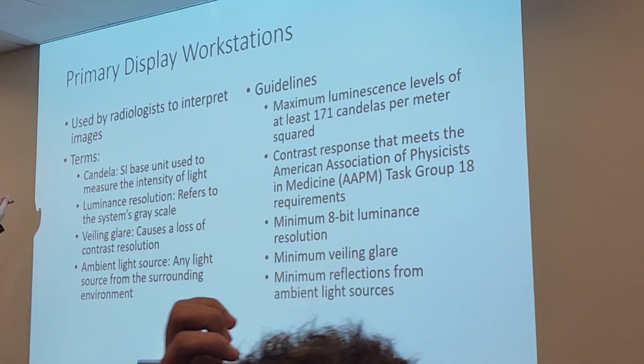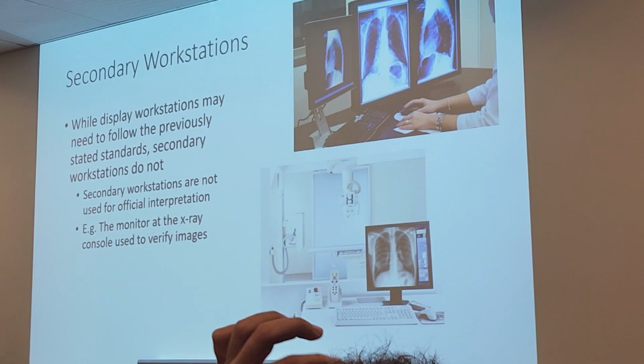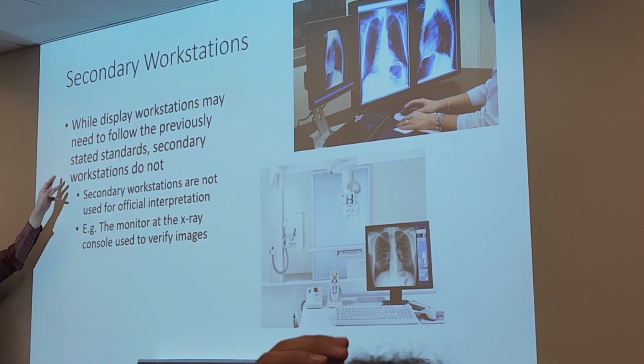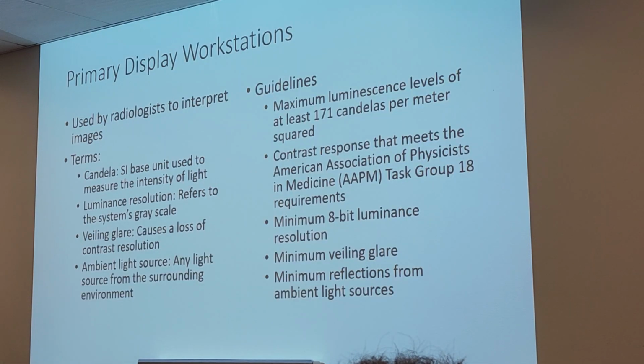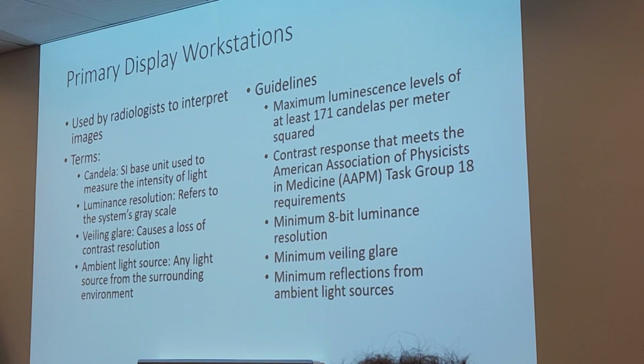There are two different types of monitors: primary displays and secondary displays. You, as a tech, are using a secondary display. Your displays do not follow the display standards. They don't need a certain brightness, they don't need a certain contrast, they don't need a certain reduction in reflection or glare. So the way you view the image is different from how the radiologist views the image, but their monitors need to adhere to these requirements.